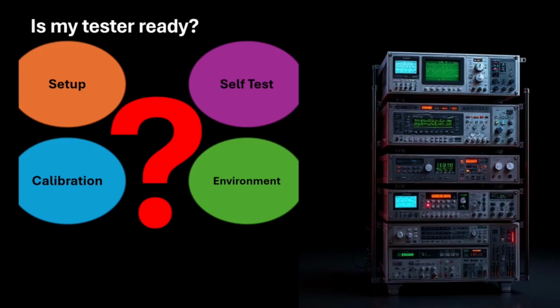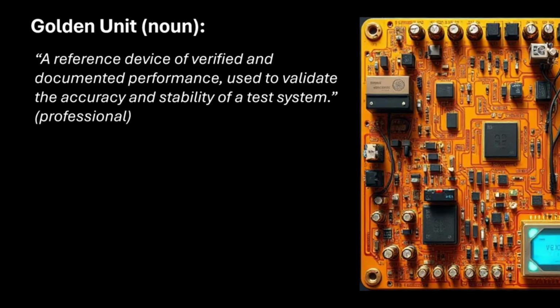The question is, I've done all these things. How do I know whether my station is ready to run the test? One of the concepts that I've learned over the years is what we call a golden unit or a reference unit, depending on your preference. I'll call it golden unit. It's a reference device whose performance you verify and document, and use to validate the accuracy and stability of the test system. After the calibrations, you test this unit and see whether, when it's supposed to pass, it passes. When it's supposed to fail, does it fail? So that's a professional definition.